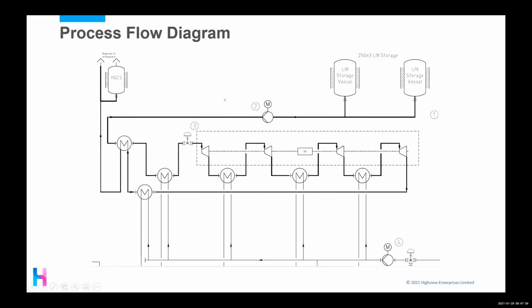So just very briefly, I'm going to talk through our process flow diagram. Here we have our liquid nitrogen storage vessels, about 250 meter cubed worth. This is at a pressure of about 10 bar and minus 170 degrees Celsius. We pressurized it to about 120 bar, which induces a small temperature increase, so it came at about minus 160 degrees Celsius.